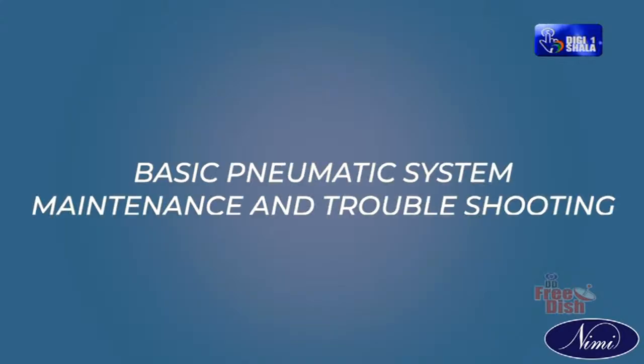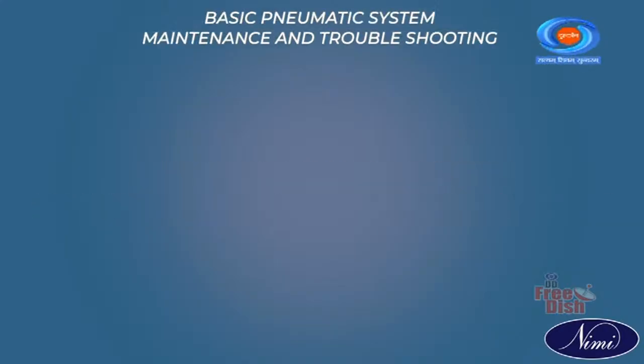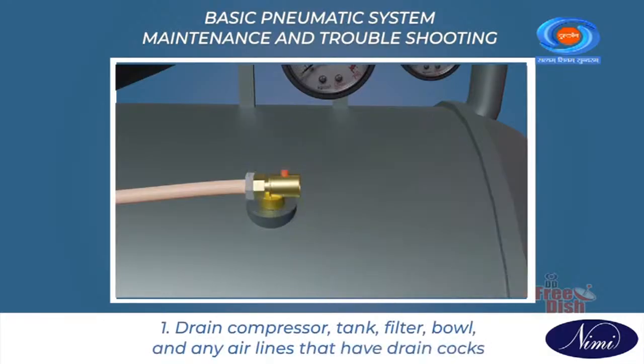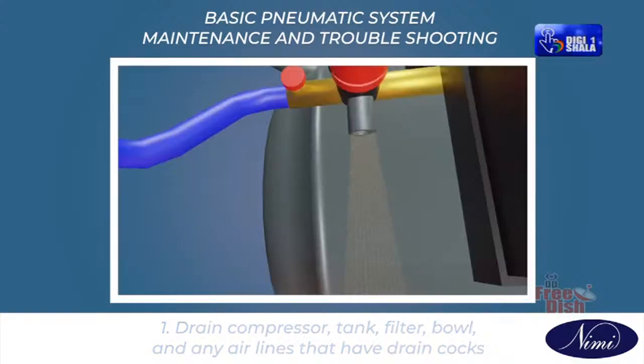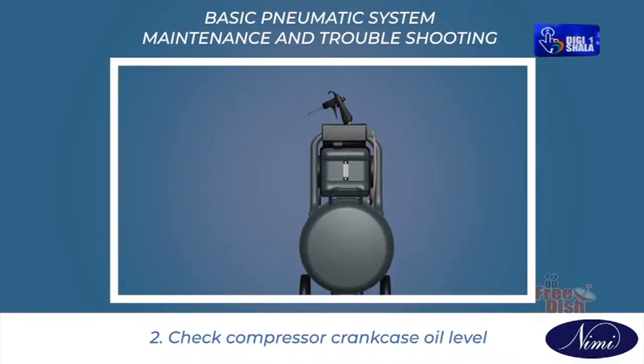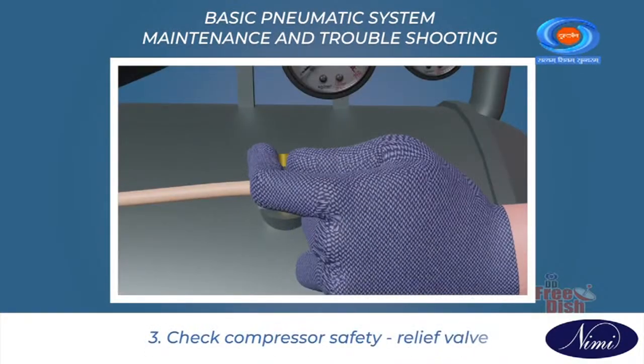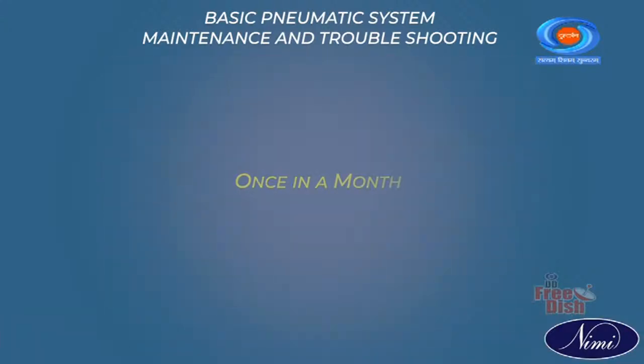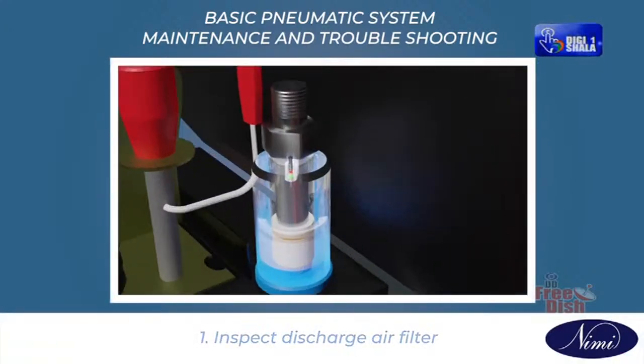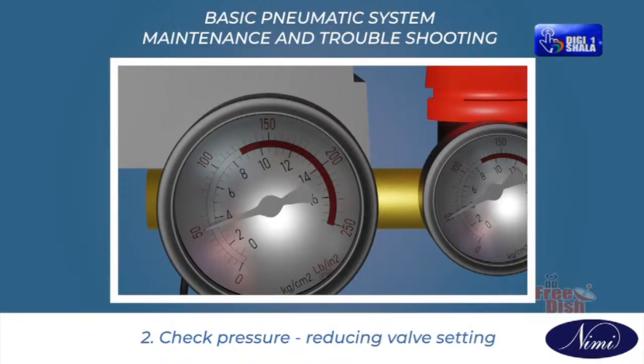Number 2. Basic pneumatic system maintenance and troubleshooting. Once in a week: drain compressor, tank, filter, bowl, and any airlines that have drain cocks. Check compressor crankcase oil level. Check compressor safety relief valve. Once in a month: inspect discharge air filter. Check pressure reducing valve setting.